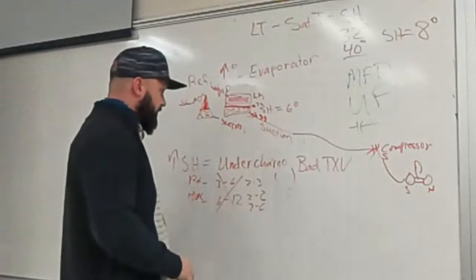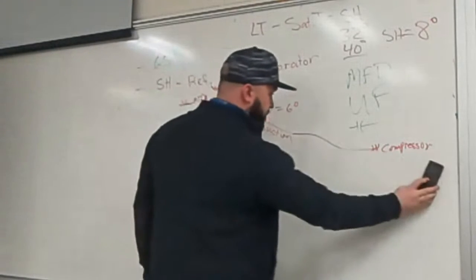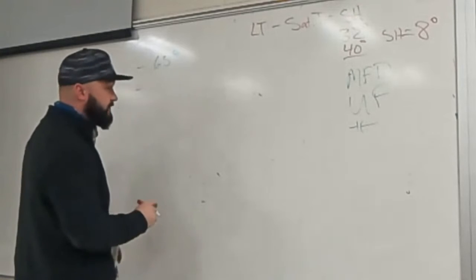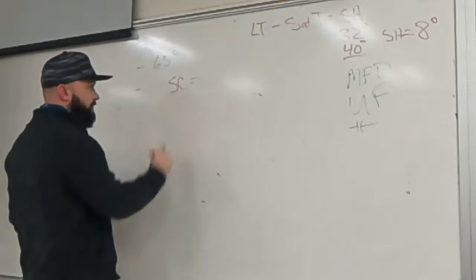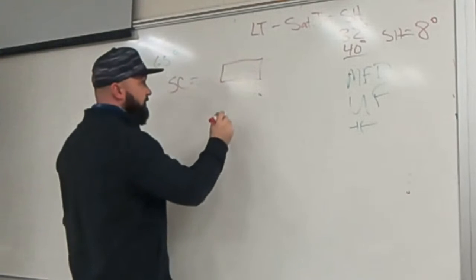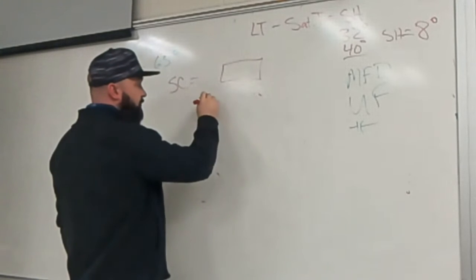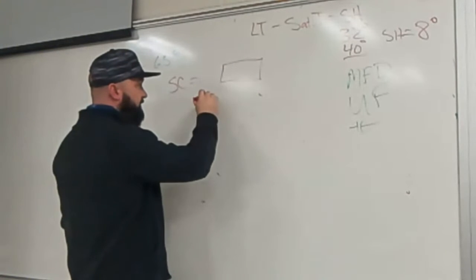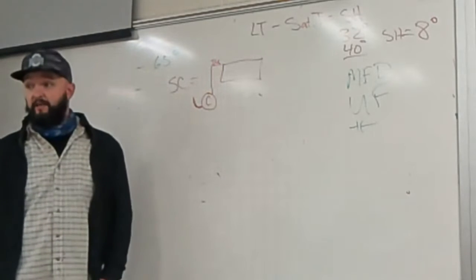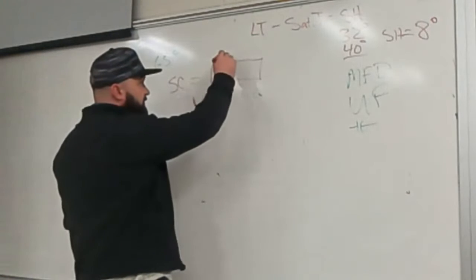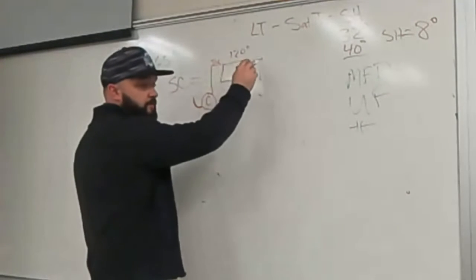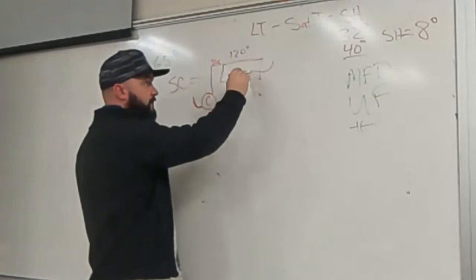Not bad at all — let's do subcooling very quickly. Subcooling is the exact opposite of superheat. Instead of an evaporator coil you have a condenser coil outside. You have a compressor with the suction line coming in, it compresses the refrigerant, and your discharge line comes out — going from low-pressure vapor to high-pressure, high-temperature vapor. Let's say it raises it up to 120 degrees.